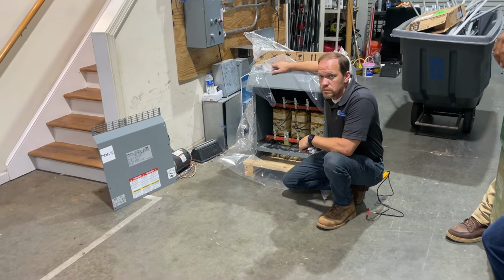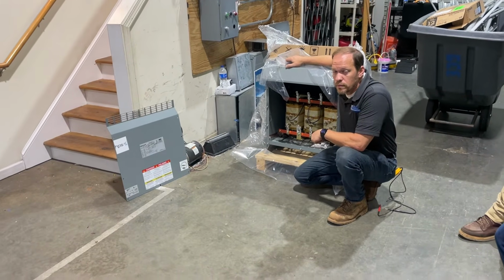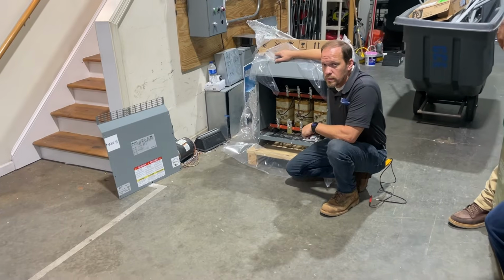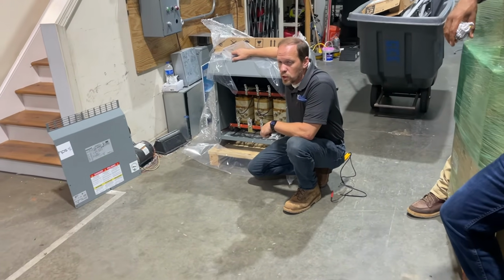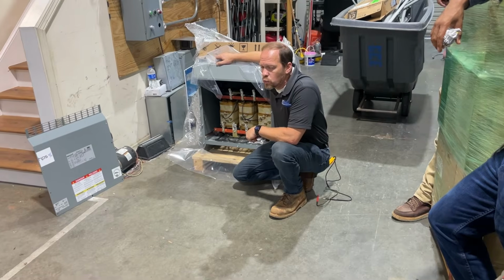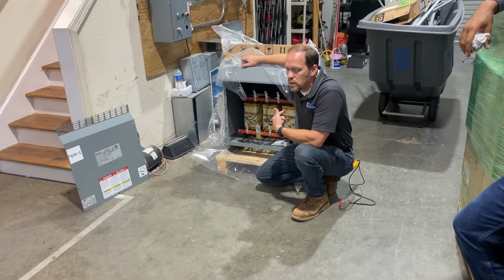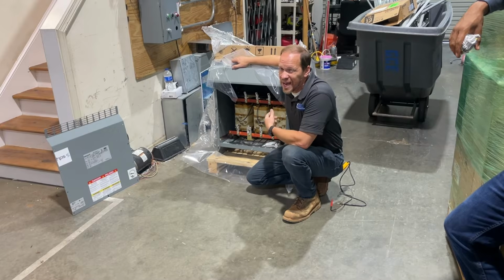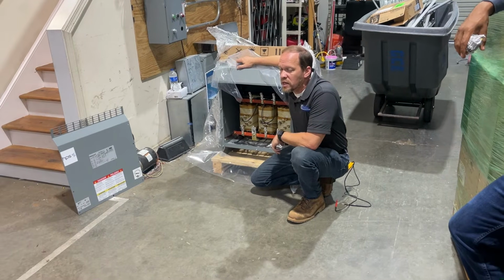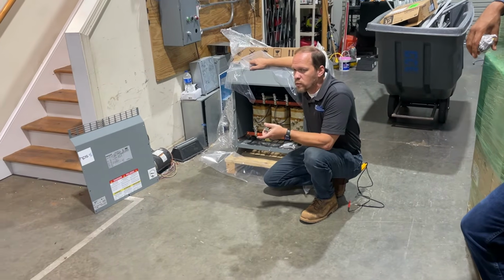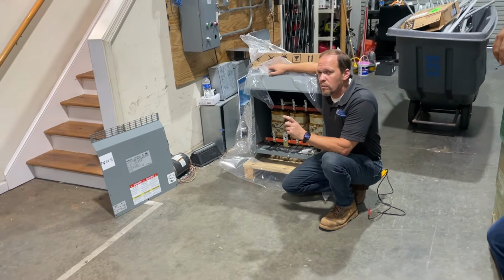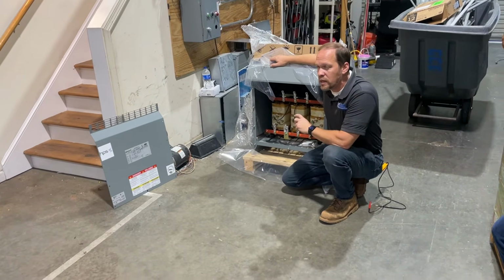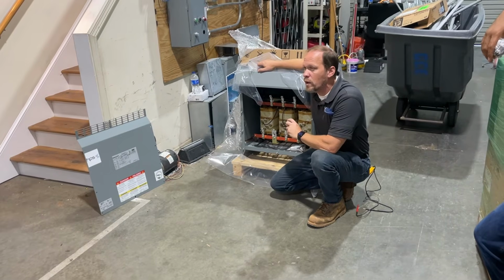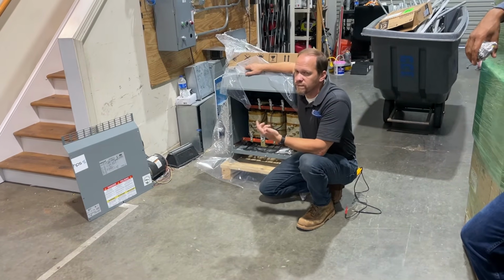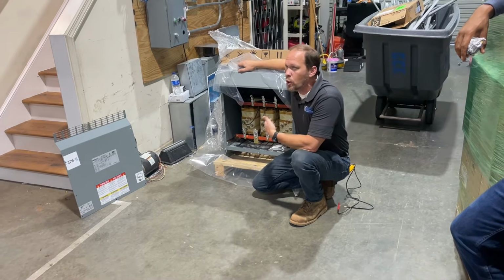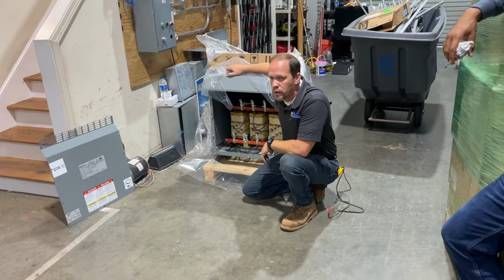Yeah, you're still gonna bond it, and that's gonna stabilize your voltages. You mentioned H, so what identifies the primary and the secondary side, what letter? In general, the H will determine what the higher voltage is, X is the lower voltage. Primary and secondary, because it works off of ratios, they can be reversed, but they're usually designed to work in one direction or the other. The only reason is because there's a voltage drop that comes from the transformer, so you'll have a little bit of a bump going one direction or the other.